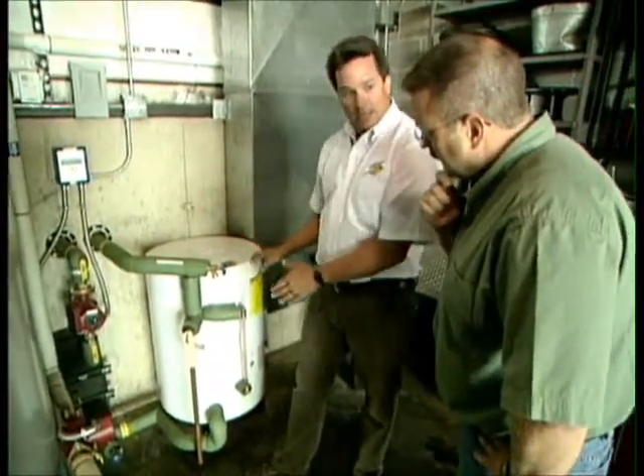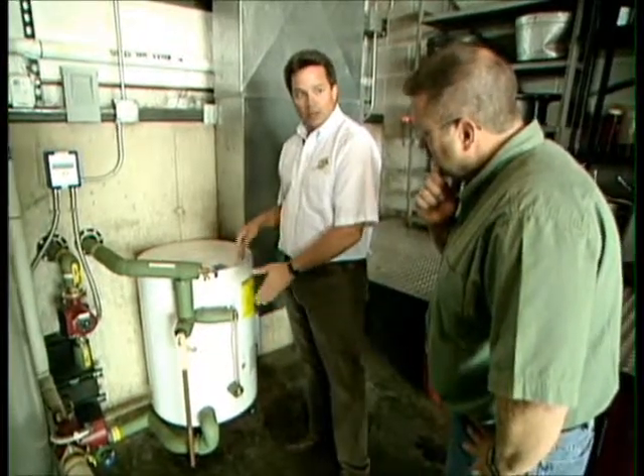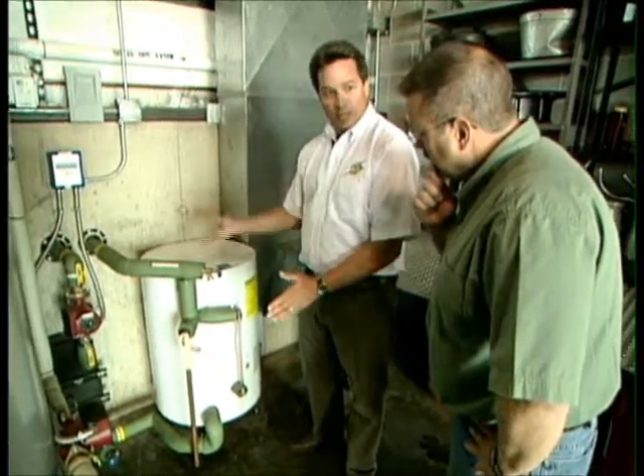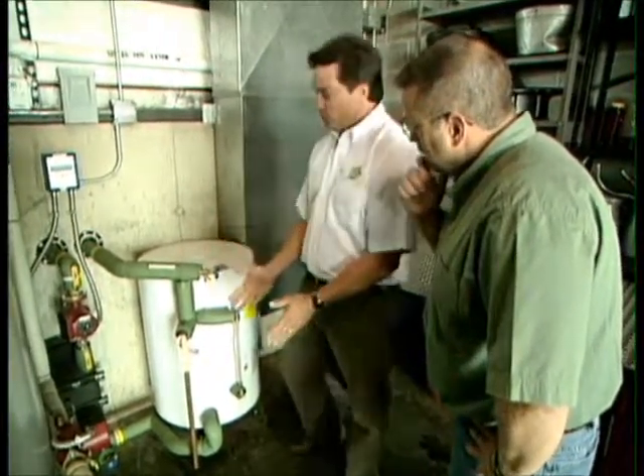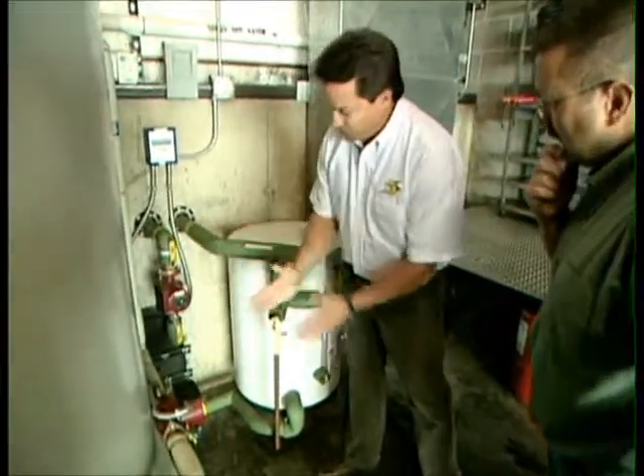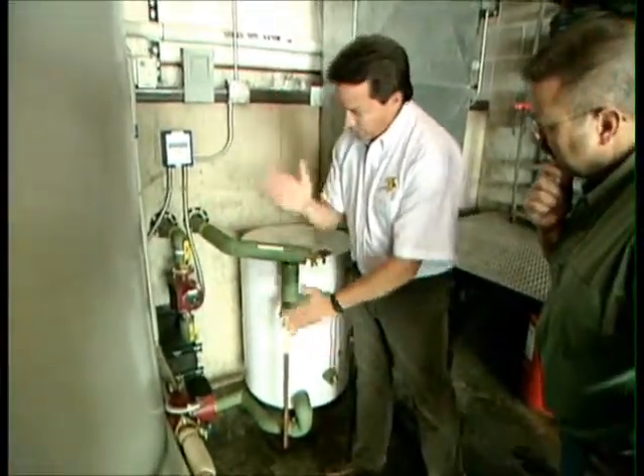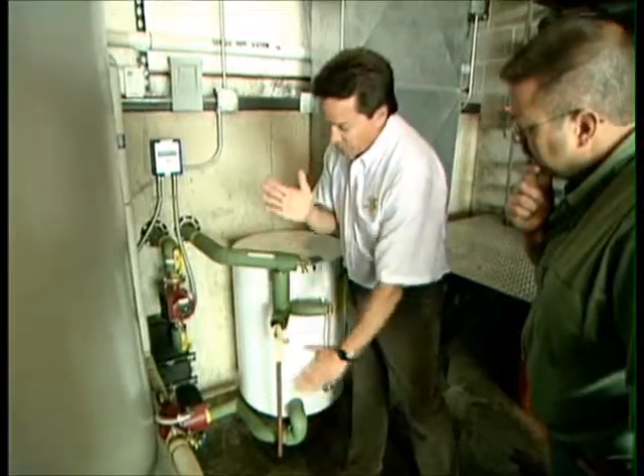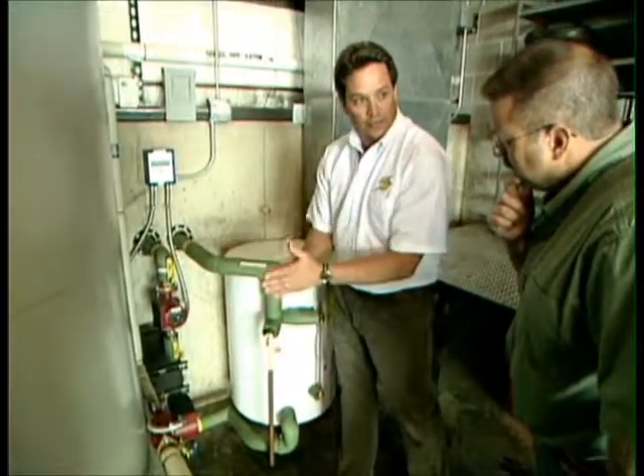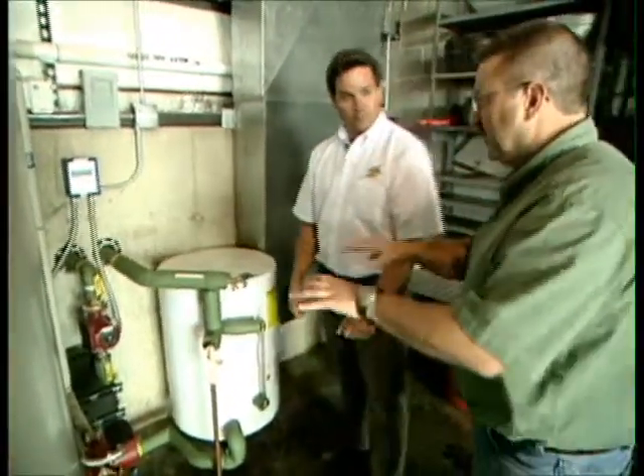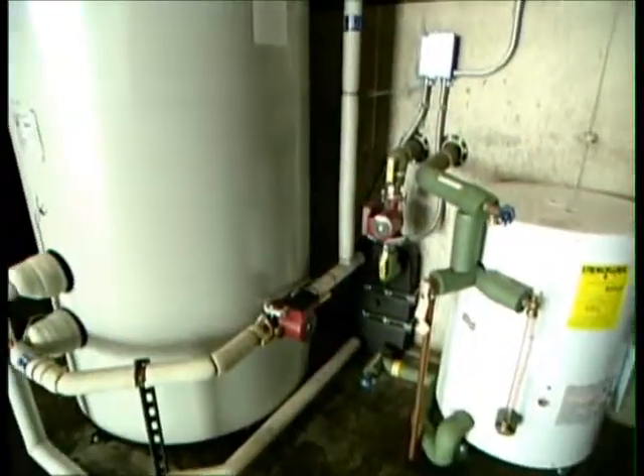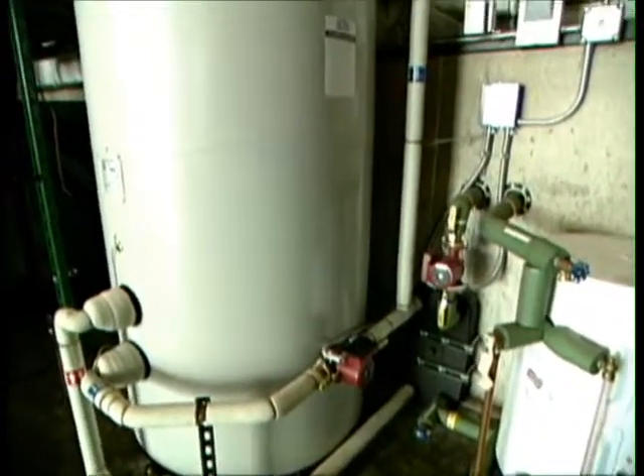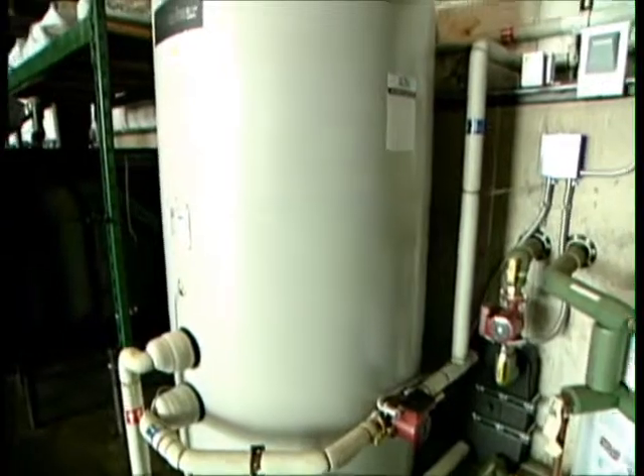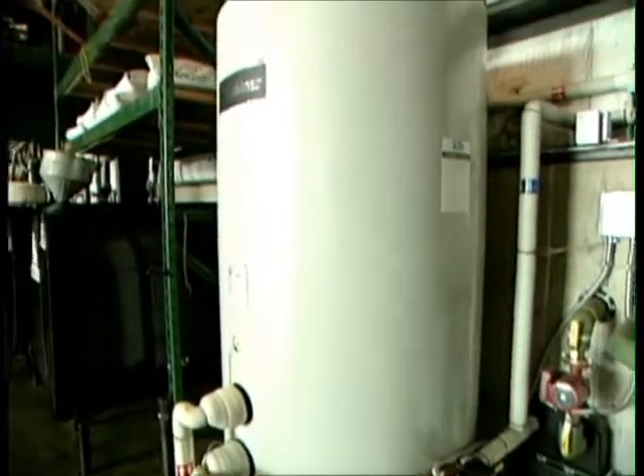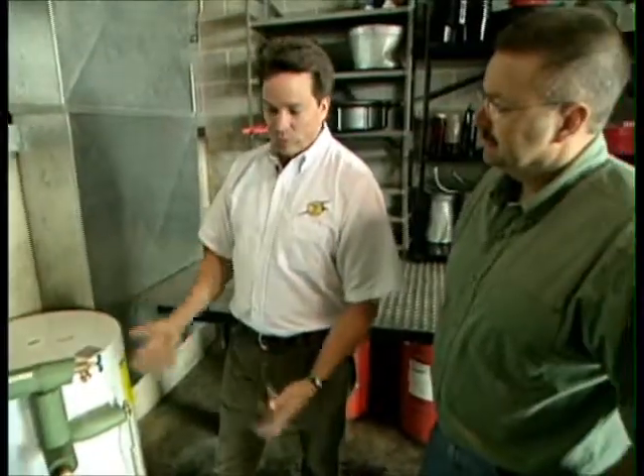Although it is a non-toxic fluid, the propylene glycol, we still want to keep our separation of the potable water and the non-potable fluid. So the plate and frame heat exchanger circulates the glycol through the plates in one direction and the domestic water back through in the other direction. That's where your heat transfer occurs. And what temperatures are we talking at here? I mean, within this, looks like about a 300, 400 gallon tank. How hot is the water getting in there? Well, right now the storage tank is sitting at 98 degrees, and within a couple of hours we'll raise that to 130 or 140 degrees.